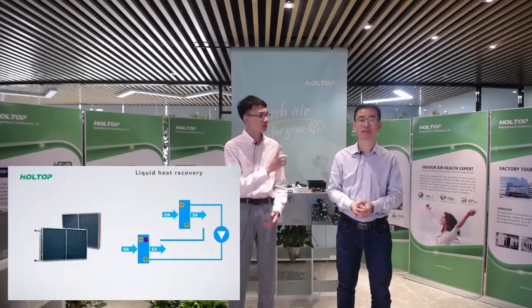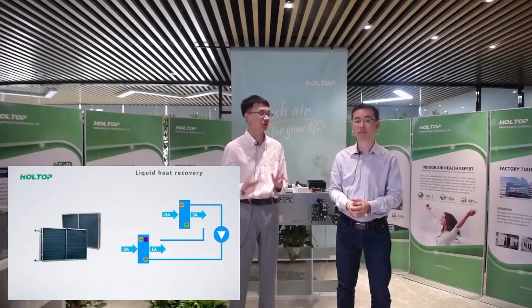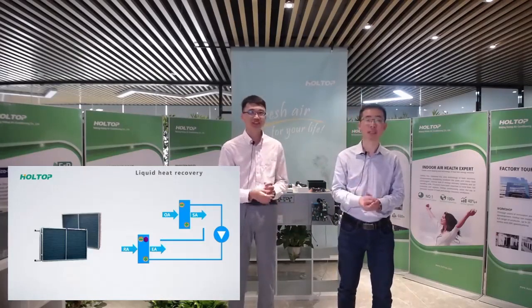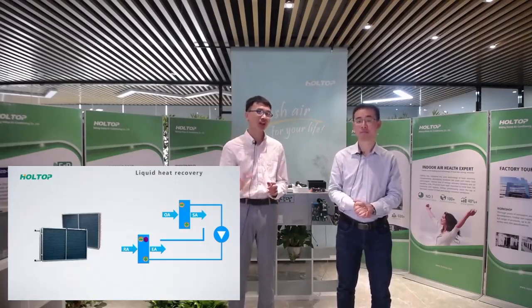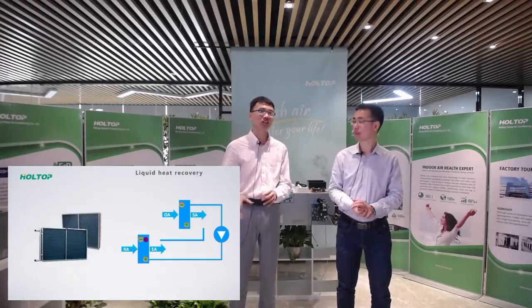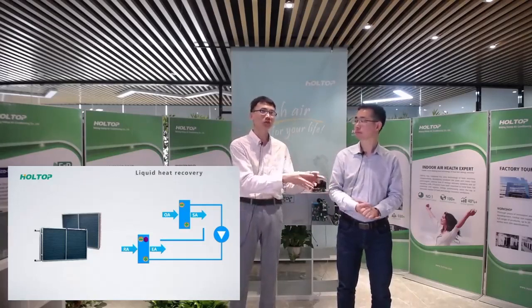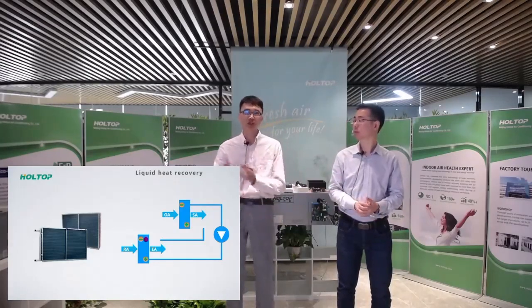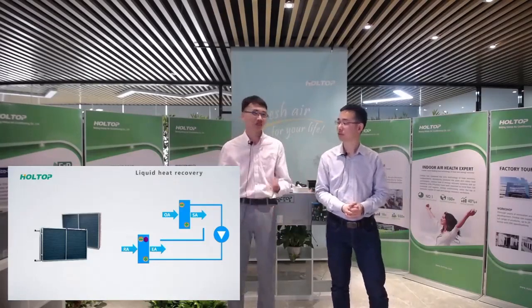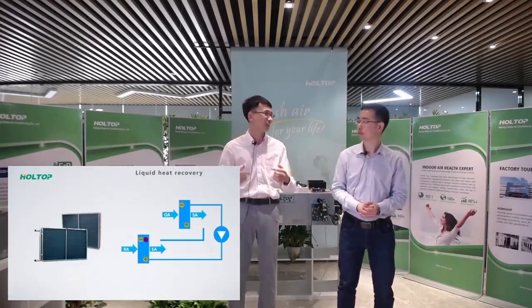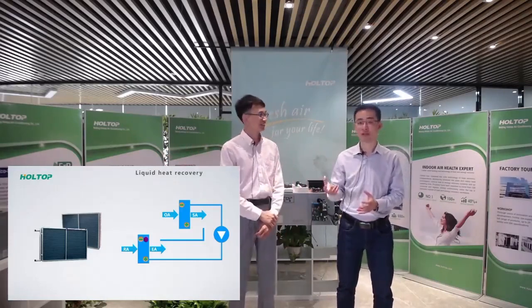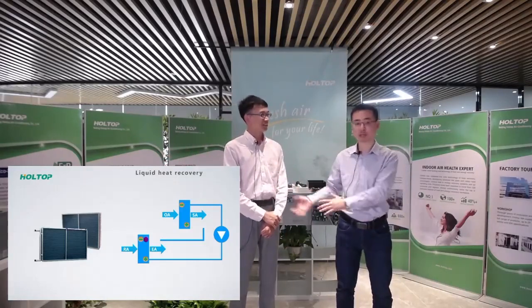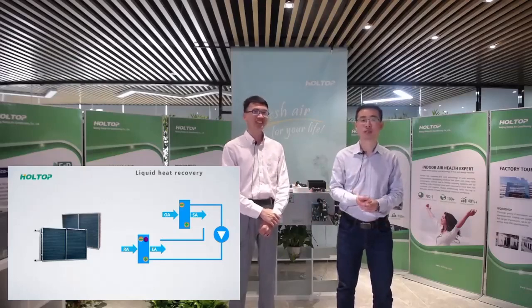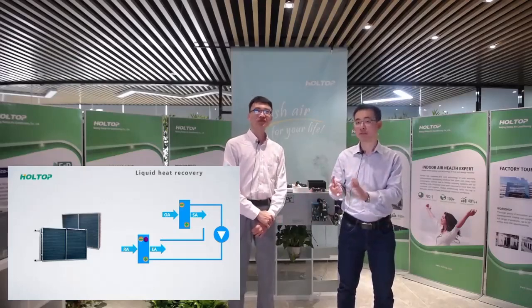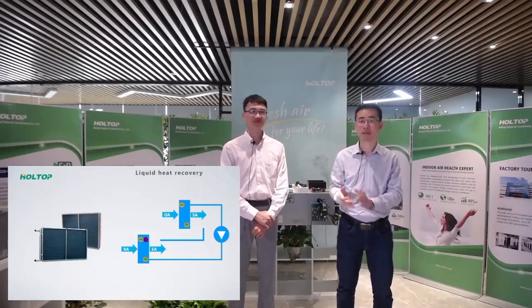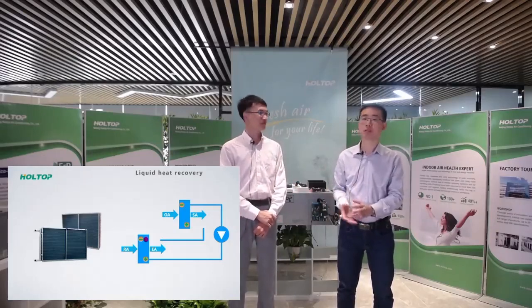So I guess this unit will be very suitable for the hospital, is it? Yeah. Because in the hospital, I found that they will set one glycol coil at one end of the building and another one on the other end. So that is a very long distance, right? Yes. As long as you have a water pump, you can pump from one side to the other side. Okay. So the above is for the flow type DX coil of AHU, the indoor unit.